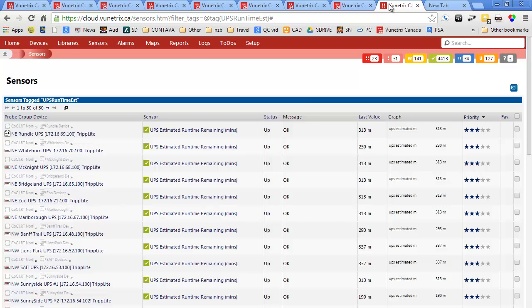We're going to see a decrease in the capacity of the UPS as we add equipment, for example, so we can monitor that. Maybe there's a threshold where we need to meet a 60-minute requirement for our UPS in case of a power failure, so we'll quickly be able to see that and identify when we add any more. If we're going to add more equipment, we're also going to have to upgrade that UPS.